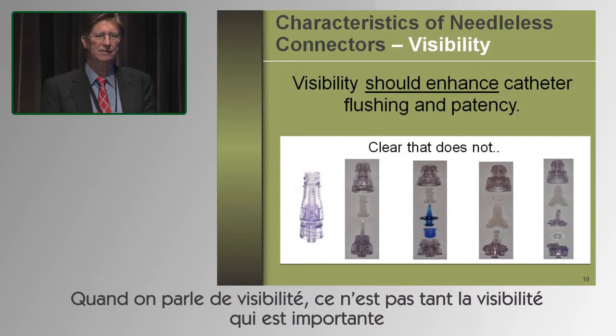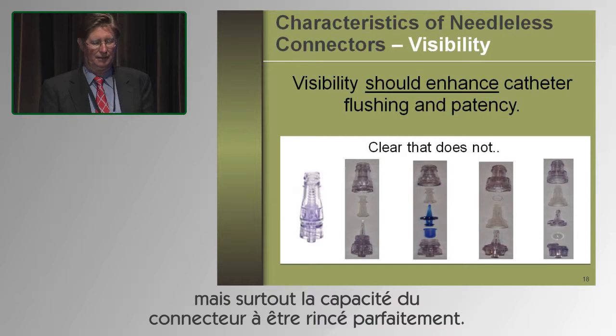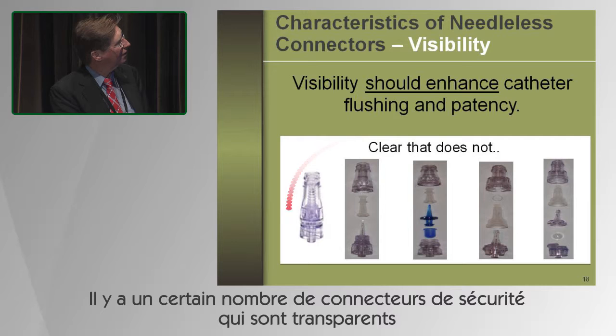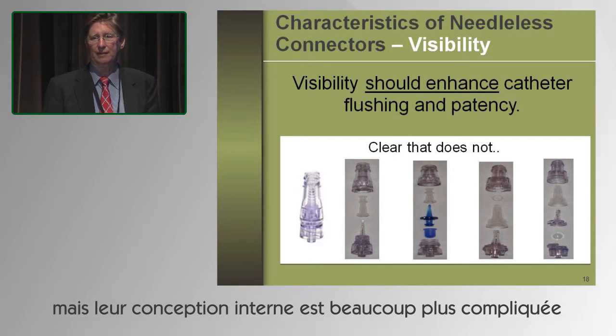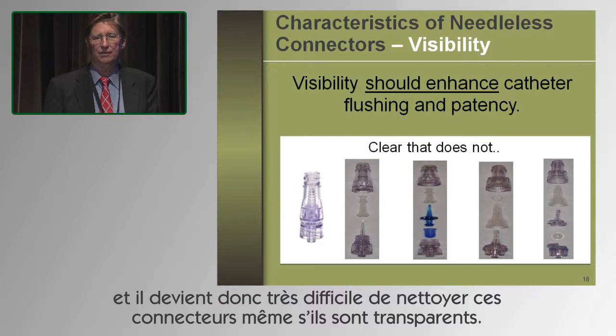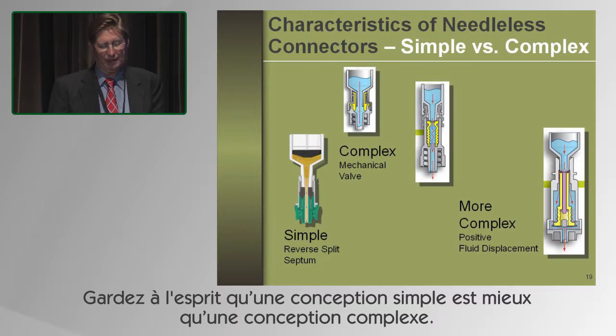So when we're thinking about visibility, it really isn't the visibility itself that's so important. It's how that translates into the ability to adequately flush the catheter. We have a number of needleless connectors that are clear. There is better visibility, but the internal design is much more complicated and therefore may be much more difficult to disinfect even though they're clear. So keeping in mind simple versus complex.